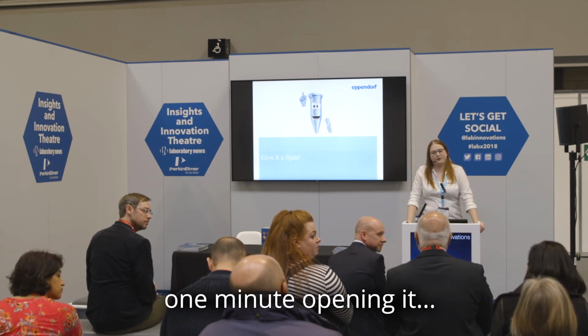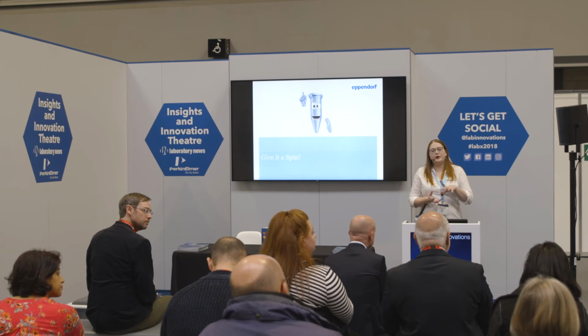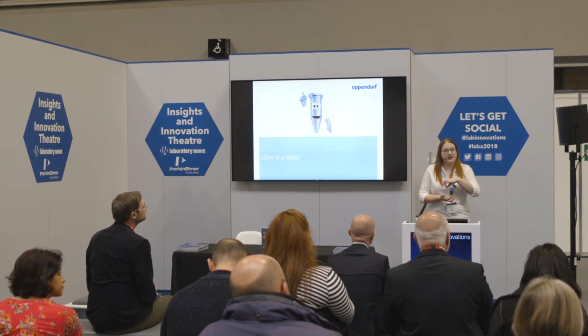The newer ones nowadays tend to have click lock. Ours have click lock, but all the manufacturers have similar systems to make it a lot quicker. Also, if you don't need aerosol tight, Eppendorf microcentrifuges are safe to spin without the rotor lid because of the technology in the centrifuge lid. So if you were doing something like a mini prep and weren't worried about aerosols, you don't have to put the rotor lid on to use it.